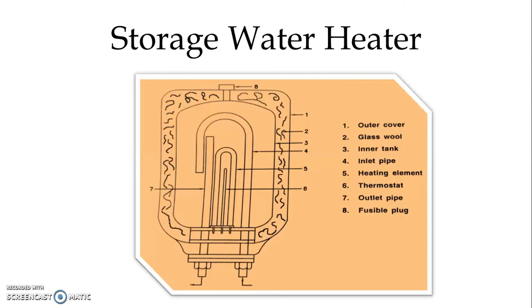In the figure we can see the construction of the storage type of water heater. We have the outer cover made of sheet steel, and on the inner side we have the copper inner tank. In between we have insulation, which is glass wool. We have an inlet pipe that takes water in, and an outlet water pipe to take hot water outside. The vertical type heating element has leads taken out for electrical connection, and we use a vertical strip-type thermostat to maintain the temperature of the water.